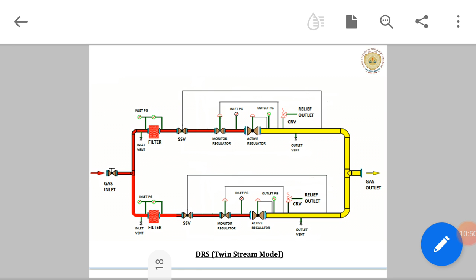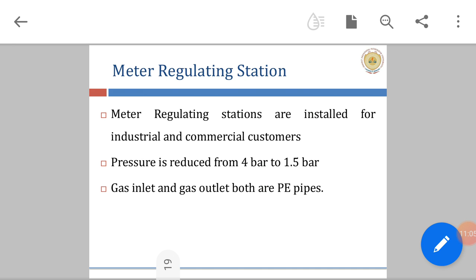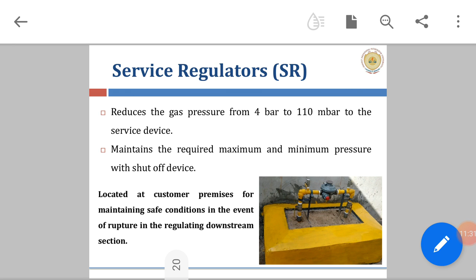The meter regulating stations are installed for industrial and commercial customers. Pressure is reduced from 4 bar to 1.5 bar. Gas inlet and gas outlet both are PE pipelines. The service regulators seen near our houses reduce the gas pressure from 4 bar to 110 millibar to the service device, maintaining the required maximum and minimum pressure with a shut-off device. They are located at the customer premises for maintaining safe conditions in the event of rupture in the regulating downstream section.